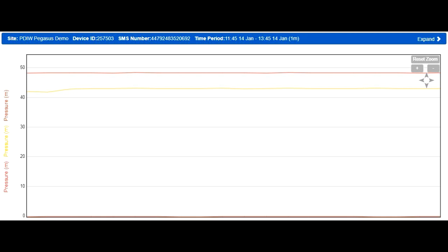What we are seeing in this zoom image is our downstream pressure, this is the yellow line, trying to reach the configured setpoint of 55 meters head. As our inlet or upstream pressure, the red line, is around 50 meters, our downstream pressure will never be able to reach what we asked for.